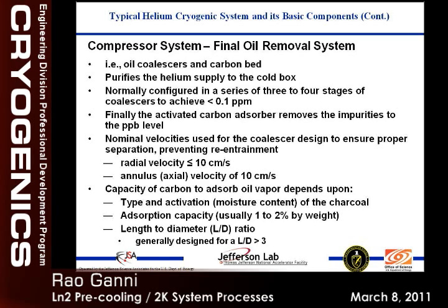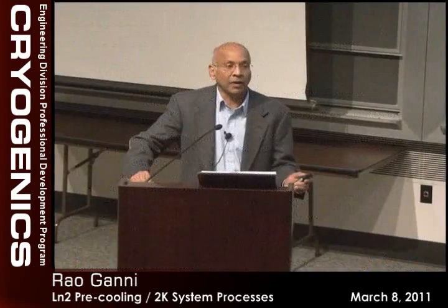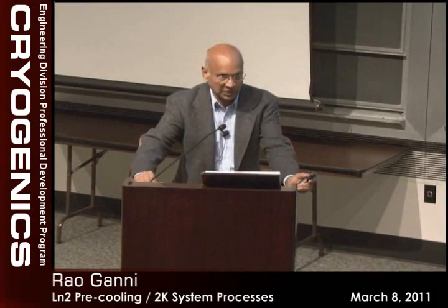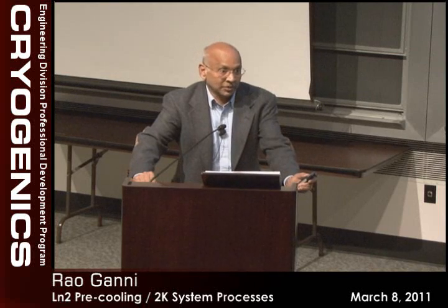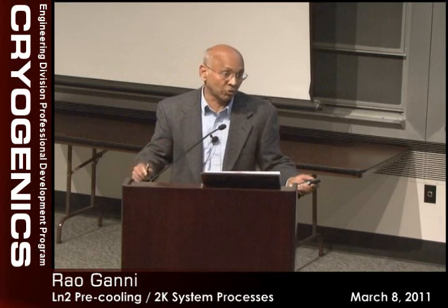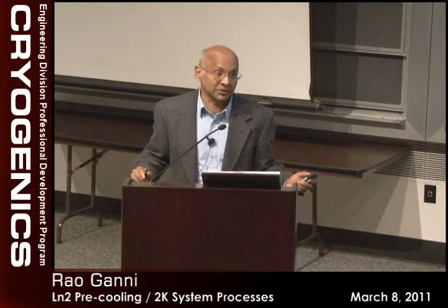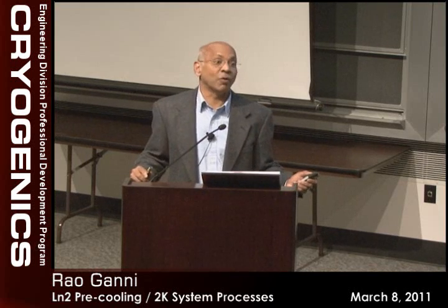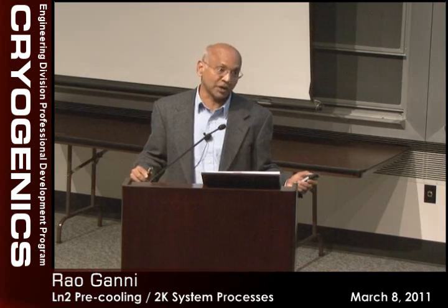Ucon oil? Yes, we have oil treatment. And why do you have to do that? Because when we get this oil, especially Yukon, it has so much moisture, water, in it. And not only that, it has light ends, as we call them, low volatile vapor fluids in it. When we compress it to high temperatures, which happens with the helium, all those don't stay in there, they come back with the gas and may pass through our charcoal, pass through the coalescers and end up in the cold box. So we want to make sure that all the light ends and the moisture are gotten rid of.